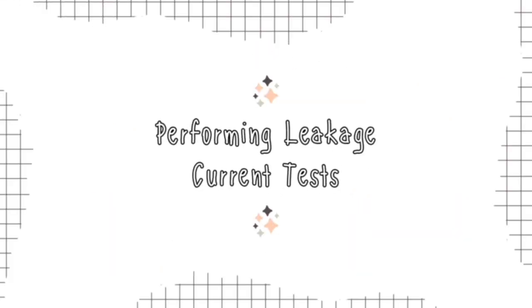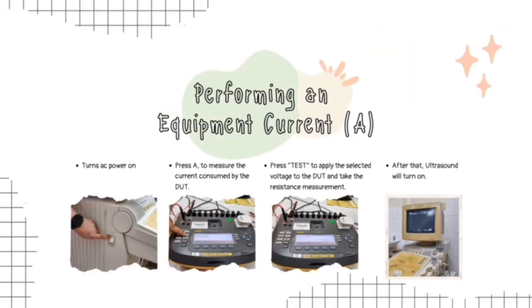Next, we will see the performing leakage current test. For the first is performing an equipment current. At first, we must turn on the AC power. Then press A to measure the current consumed by the DUT. Press test to apply the selected voltage to the DUT and take the measurement. And then ultrasound will be turned on.